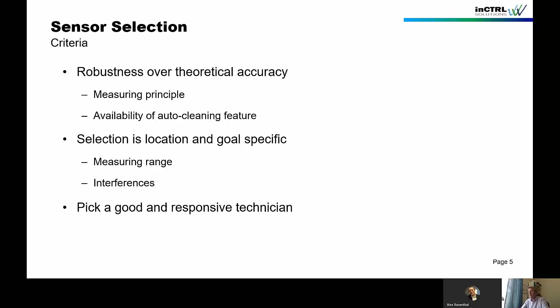There's always a discussion of cost, right? And very often it starts with the price of the sensor. I want to make sure you understand that this is really not the main cost of operating sensors. The main cost is actually maintenance and quality control, as you'll see on the next slide. My rule of thumb is still 1 to 2 hours per week per sensor, and do the math - that's quite some time going into your sensors.